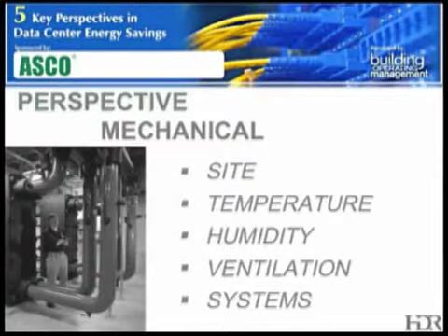And if you do have a need for dehumidification, say you were in a very humid zone and you did want to dehumidify, then I would decouple that from your main sensible cooling system, such that you'd have either a standalone DX, or you could even put in a booster chiller to lower the chill water temperature to that particular piece of equipment or that air handler that's really bringing in the outside air and doing the dehumidification that you need. Ventilation, that's a pretty broad topic.